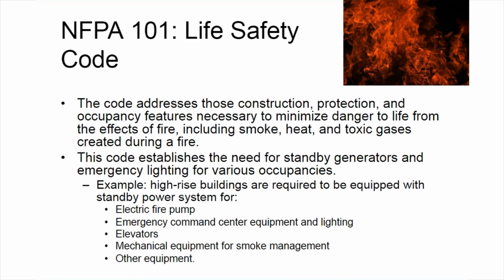As another example of the ways the codes are intertwined that are often confusing is NFPA 101 7.9, which dictates the requirements for emergency lighting. You need to dig deeper in the other codes to understand where it is applicable. Additionally, it requires emergency illumination to operate for a minimum of 1.5 hours. It is up to you to go back to 110 again and figure out what level, type, and class EPSS satisfies this requirement.